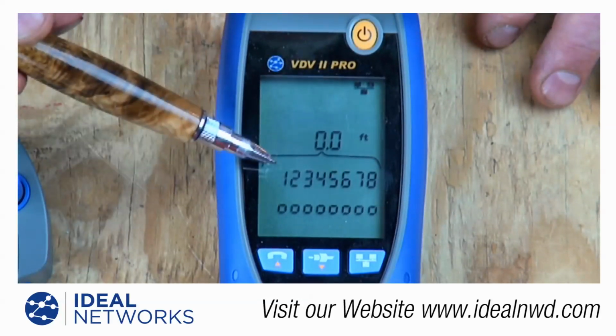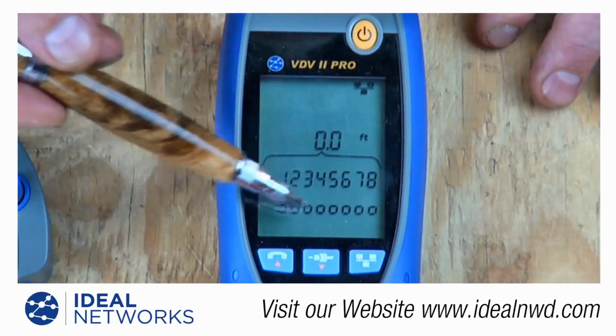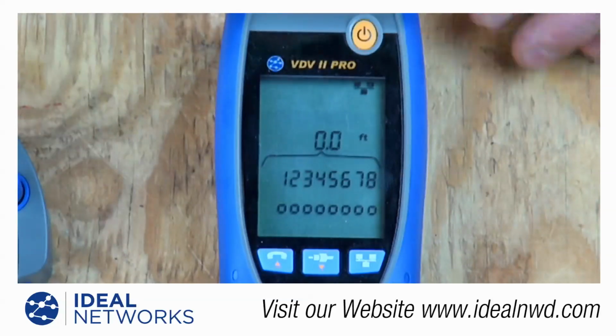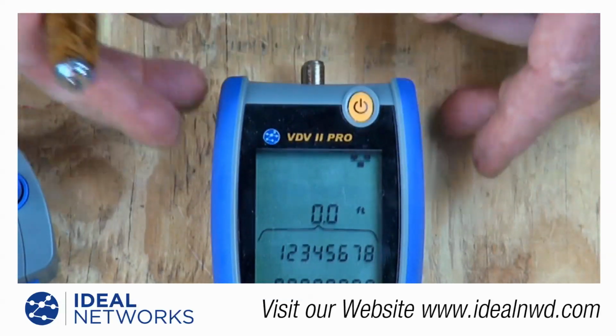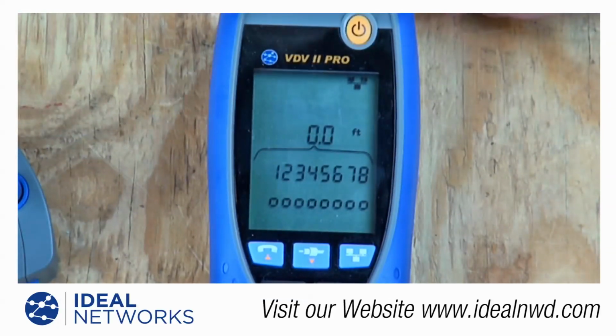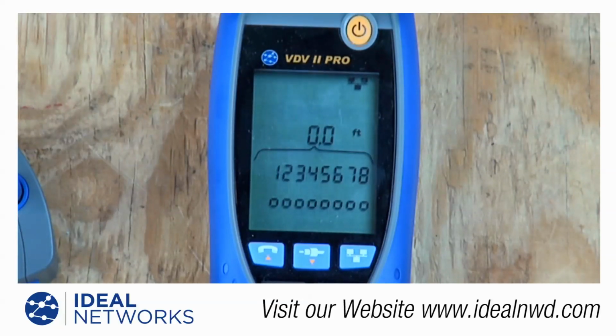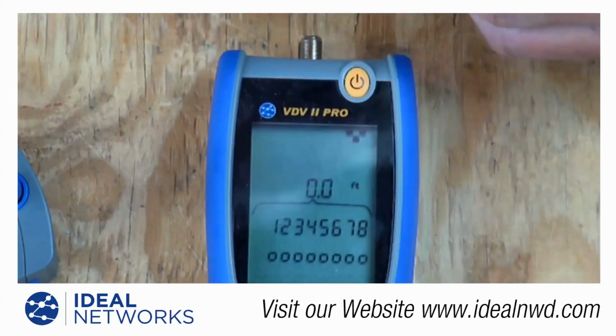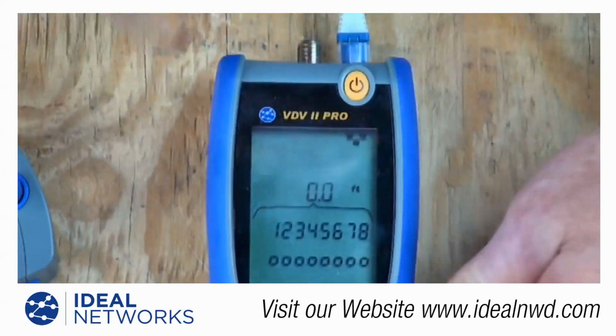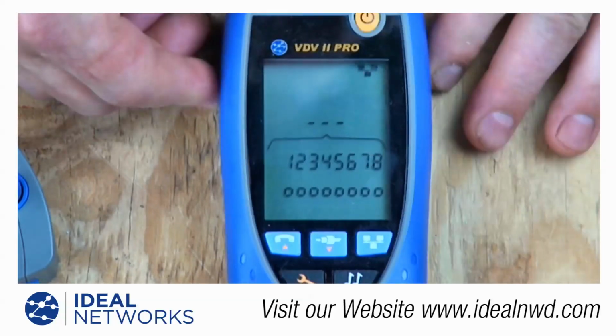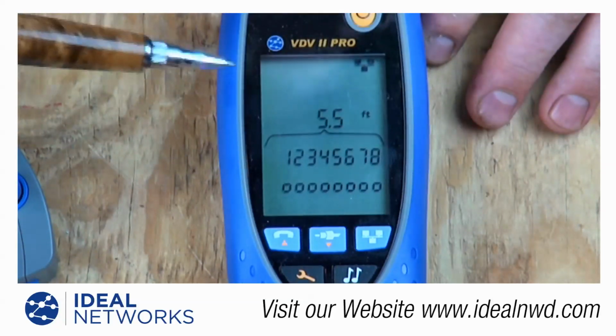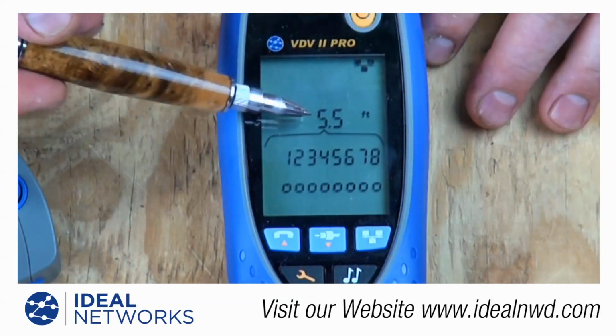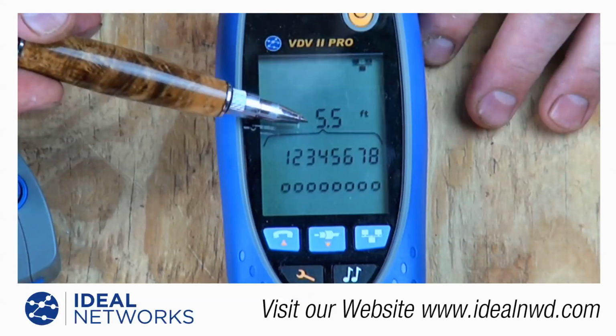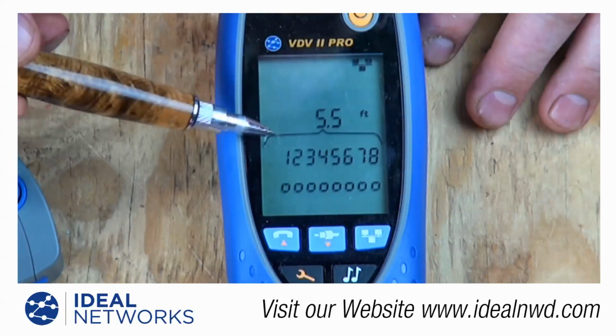It shows two rows of numbers: the top row is what it's supposed to be, and the bottom row is what it actually is. Since nothing is plugged into the top of the tester, it's not showing us anything. So I'm going to plug a known length of cable or patch cord into the top end of the tester. Now the tester shows a bit more: it sees a cable, about 5.5 feet in length, and shows two rows of numbers again.